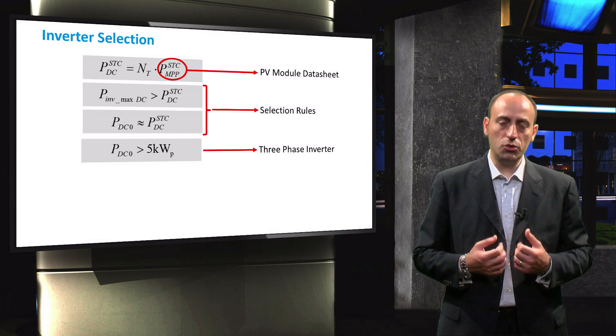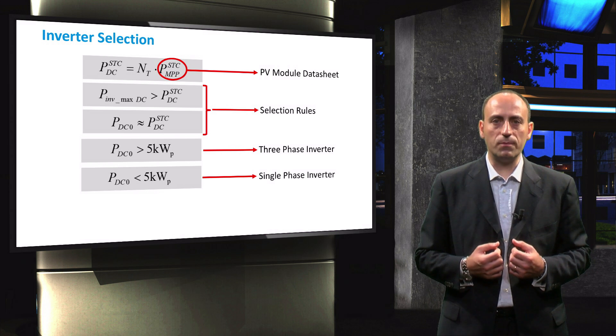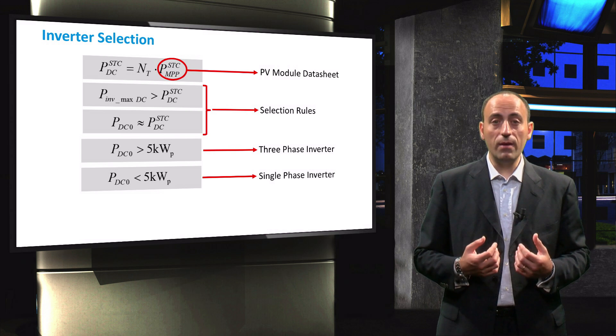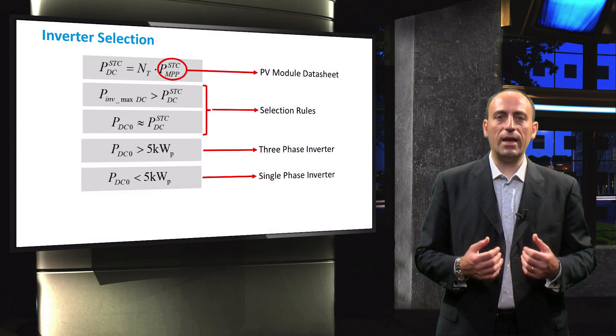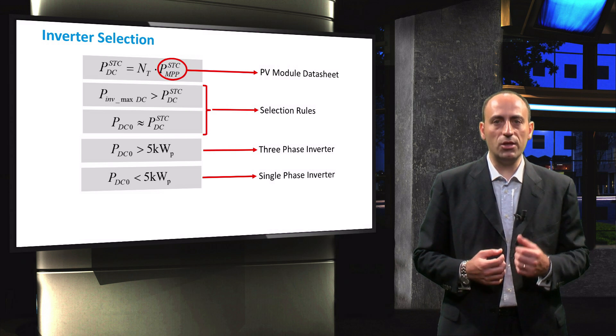An additional consideration is whether to use a three-phase or a single-phase inverter. If the inverter nominal DC power is greater than 5 kW peak, then a three-phase inverter should be used. Otherwise, a single-phase inverter is just sufficient.